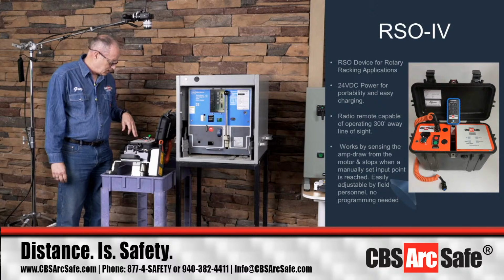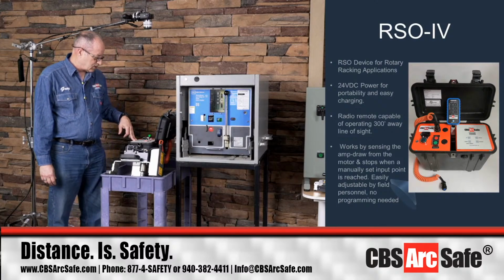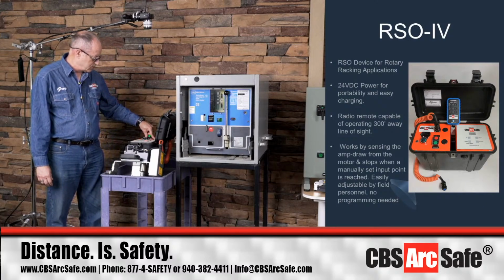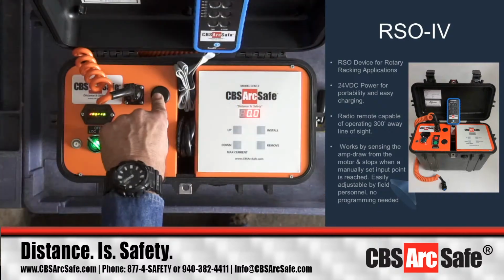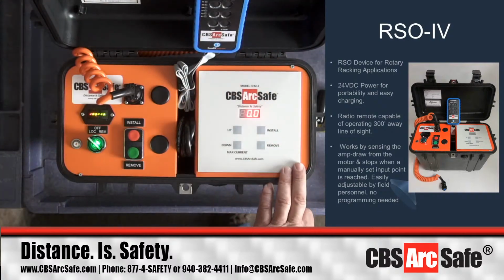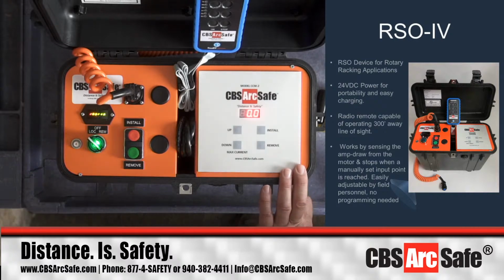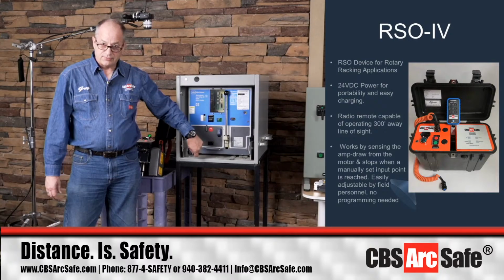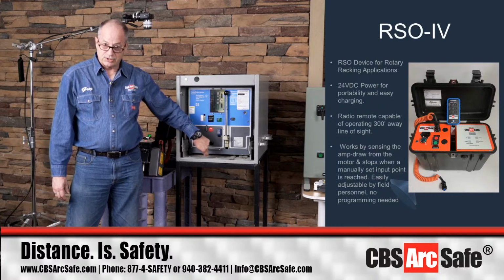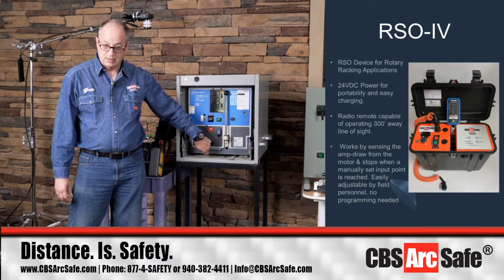to the lever. So the other options that come with this are, you notice that there's two holes here, and there's additional buttons that we can put on things, and those are based upon whether or not you have an interlock. So on a Masterpact NW, down at the base of it, for each position that you have to push in and reset a little white plastic tab so that it allows you to progress from connect to test to disconnect, or vice versa going back in.